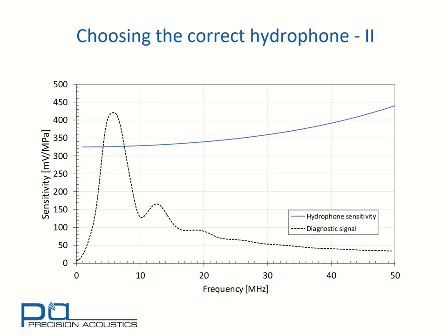We'll now consider a membrane hydrophone, starting with that difficult case of the diagnostic signal. One can see that even though there's quite a lot of variation in the source signal being measured, there's very little variation in the hydrophone sensitivity. And if anything, where the acoustic signal has spectral content diminishing, there's an increase in sensitivity with the membrane hydrophone. Membrane hydrophones are an ideal choice for measuring broadband diagnostic signals.